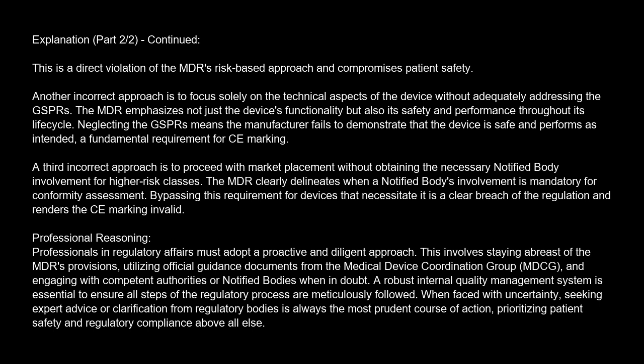A third incorrect approach is to proceed with market placement without obtaining the necessary notified body involvement for high-risk classes. The MDR clearly delineates when a notified body's involvement is mandatory for conformity assessment. Bypassing this requirement for devices that necessitate it is a clear breach of the regulation and renders the CE marking invalid. Professional reasoning. Professionals in regulatory affairs must adopt a proactive and diligent approach.